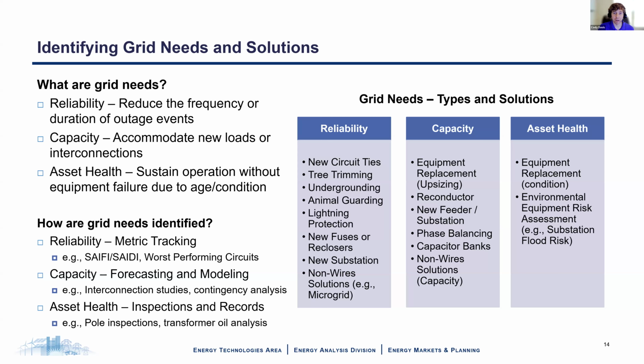On the capacity side, generally we're either upsizing existing equipment, replacing equipment with larger conductor, or adding a new feeder or a new substation. You may also consider things like non-wire solutions, or general phase balancing ways to extend the life of your existing equipment. And then on the asset health side, the most common method is just replacing the thing that's too old to continue functioning. But there is also an element of considering different types of environmental risks here as well.